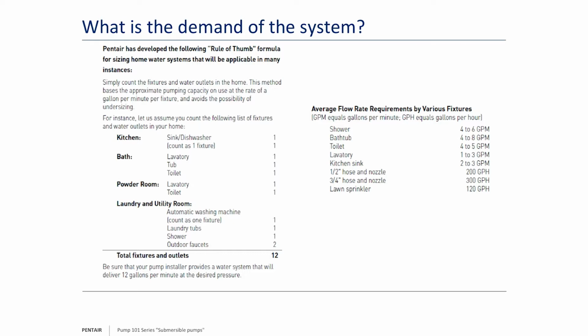saying, hey, this is ridiculous. Can we not show them how they need less gallons per minute? And I'll tell you, the simple answer is you have to adhere to local code. If that specifying engineer tells you need that many gallons per minute, we unfortunately have to do it. So believe it or not, basically a dental office / residential home, we had to size them a 78 gallon per minute pump. So that's why, again, I tell you, there's no magical bullet.